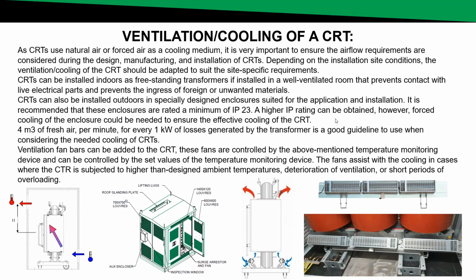If the installation area is well ventilated and prevents contact with live electrical parts and prevents the ingress of foreign or unwanted materials. Cast resin transformers can also be installed outdoors in specially designed enclosures suited for the application and installation. It is recommended that these enclosures are rated at a minimum of IP23. Higher IP ratings can be obtained for these enclosures.